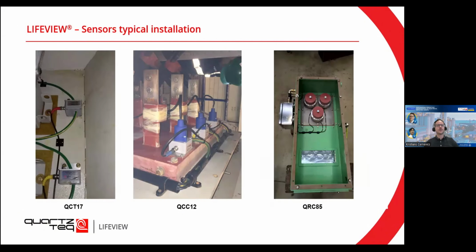And just here to show you some typical installations. On the left side, you can see the current transformer installation. You can see that the green-yellow wire is going from the surge capacitor through the current transformer and then to the earth. And then from the current transformer, there's a red marked cable and a yellow marked cable going for each of the two phases. And this cable then goes to your analyzer, your PDA2.